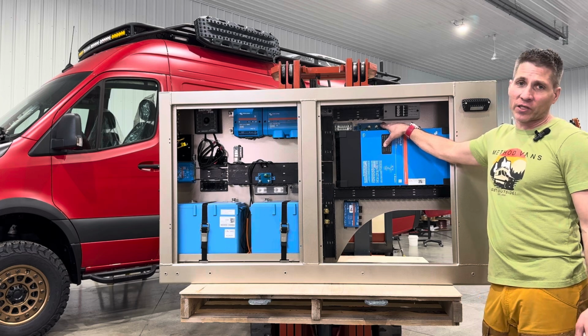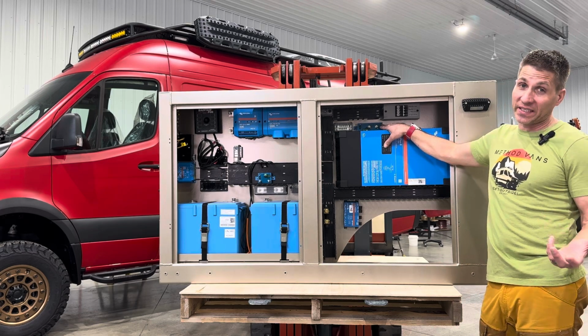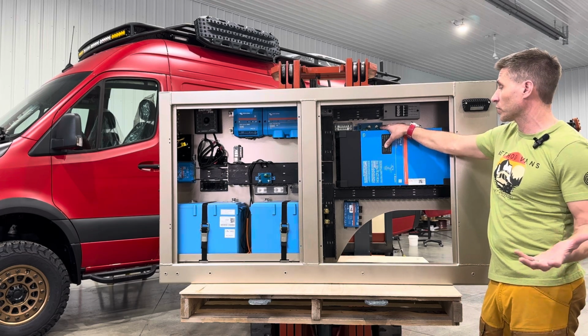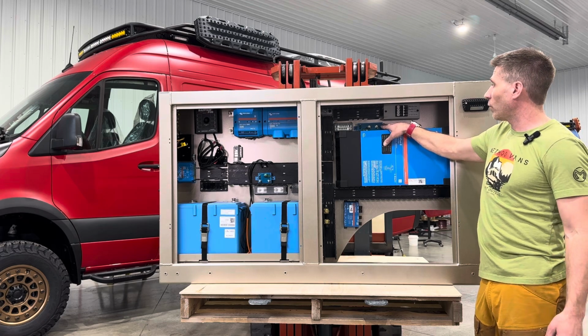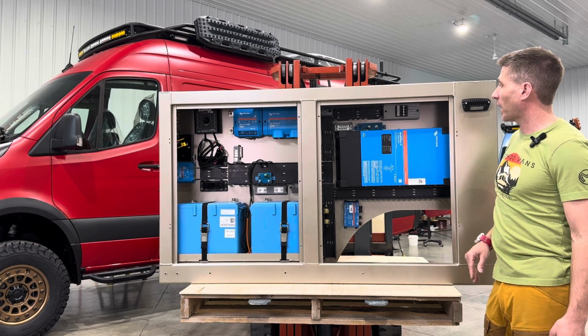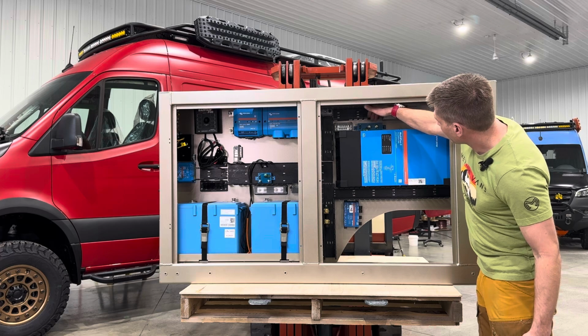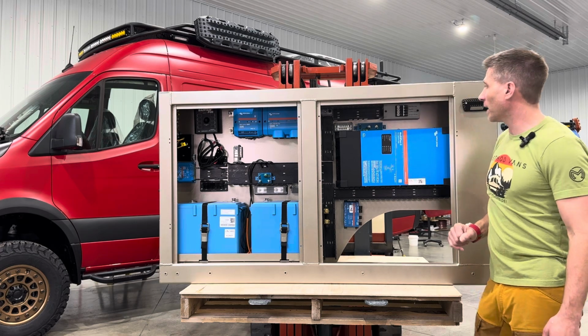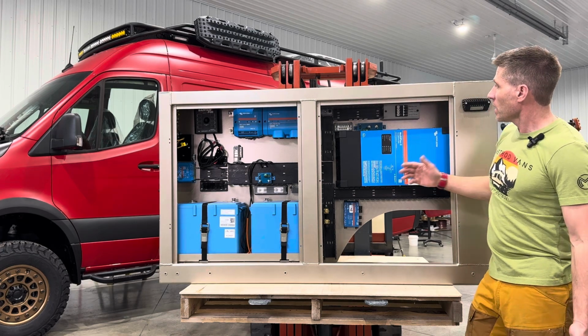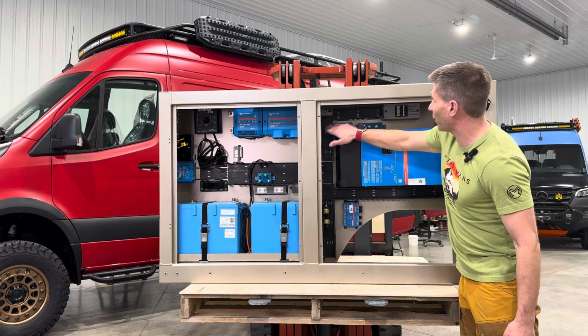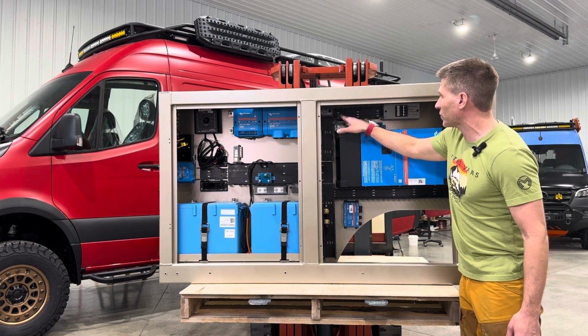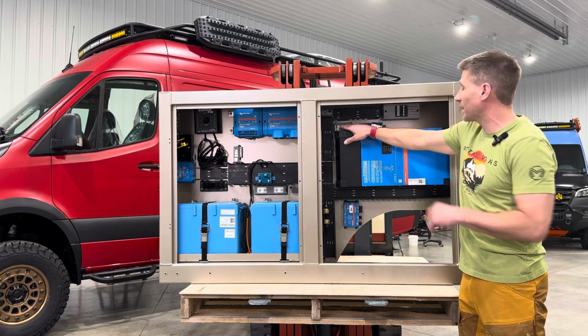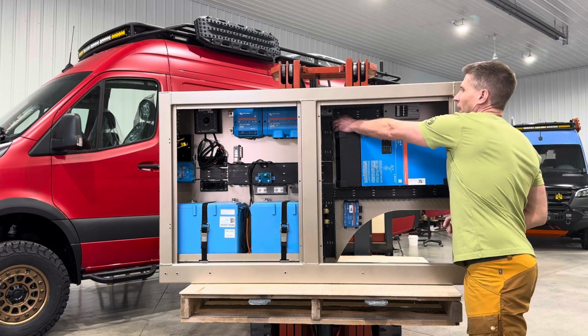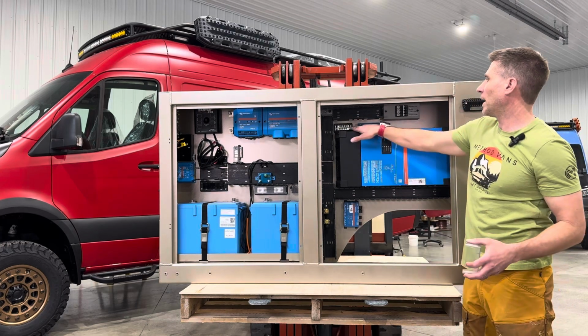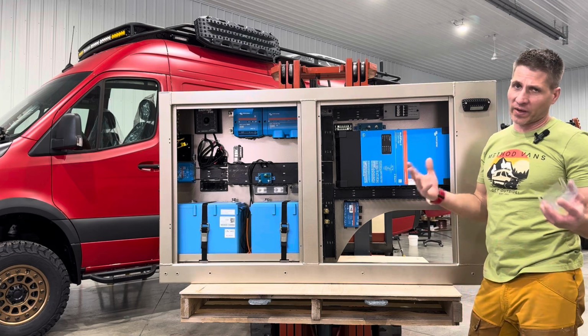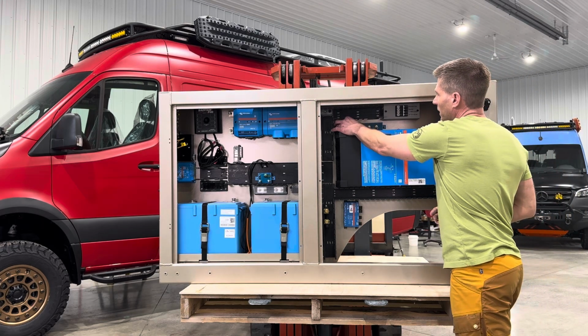Below here we have our Smart Battery Protect for all of our DC loads, so our direct current loads, which is a 12-volt system. All of that will be coming out of this Battery Protect. Again, we've got openings for all of our wiring in and out of this. In addition to this negative bus bar, we have another negative bus bar, and these two will be attached together. This gives us a bunch more connection points for negative components. We end up with a lot of negative leads inside this system.